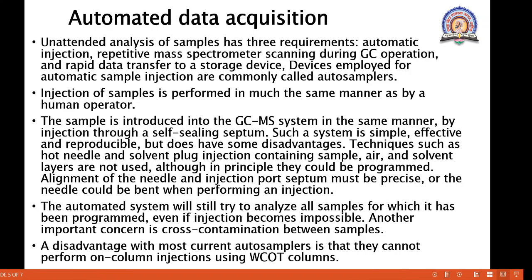The sample is introduced into the GCMS system by injection through a self-sealing septum. Such a system is simple, effective, and reproducible, but does have some disadvantages. Techniques such as hot needle and solvent plug injection containing sample air and solvent layers are not used, although in principle they could be programmed. Alignment of the needle and the injection port septum must be precise.